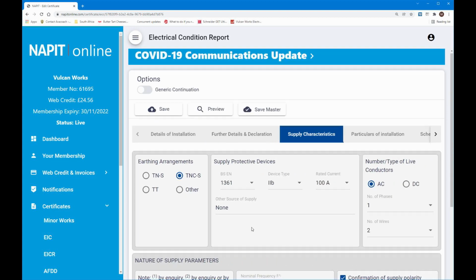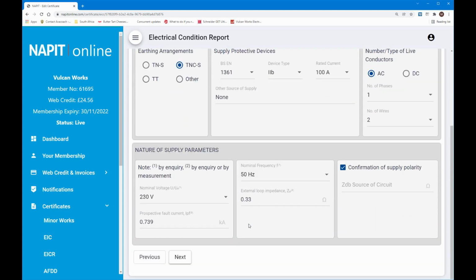Next page. So we have a TN-C-S system, as you've seen in the video, and so the protective device is a BS 1361 type 2B at 100 amps. There's no other source of supply. It's an AC system. Number of phases is 1. Number of wires is 2. So now we come down to the supply parameters, which is down here. Now it's a 230 volt supply.